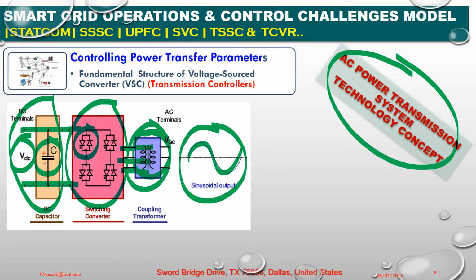With the voltage source converter, the magnitude, the phase angle, and the frequency of the output voltage can be controlled. As we know, since the direct current in the voltage source converter flows in both directions, the converter valves have to be bidirectional, and since the DC voltage does not reverse, the turn-off device need not have reverse voltage capability. Okay, so on my next slide we are going to discuss the 3-level 48 pulse modulation mode.